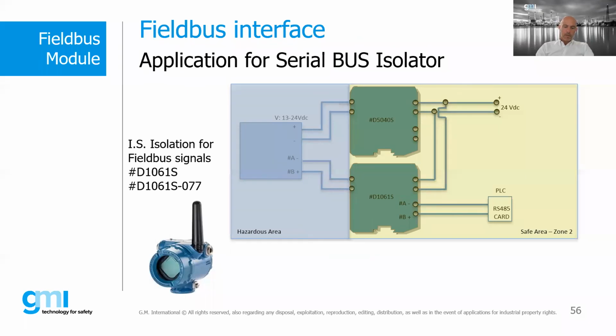Okay. In this slide, we examine an application where a sensor installed in a hazardous area must communicate via RS485 with the control unit located in a safe area. The sensor located in the hazardous area must be isolated and powered through two barriers. One barrier will supply power to the classified area so that the sensor is protected and cannot generate sparks that can cause an explosion. The other barrier will have to provide isolation of the RS485 bus line so that it can connect with the control unit.